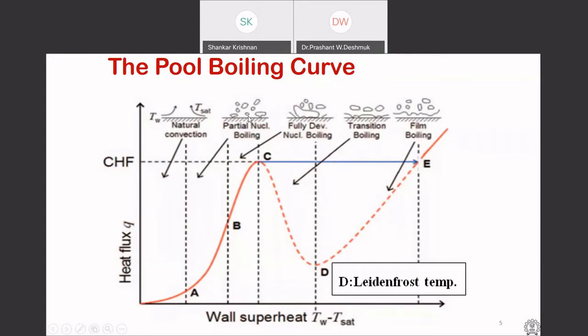The bubbles start to coalesce and form larger and larger bubbles — that is fully developed nucleate boiling. At some point it reaches what is called a hydrodynamic limit, where suddenly a vapor blanket covers that surface. Because the amount of heat flux put into the device is so high, the liquid returning from condensation is cut off and cannot be supplied for vapor generation. At that point you reach what is called the critical heat flux.